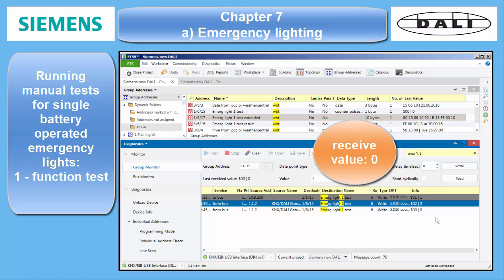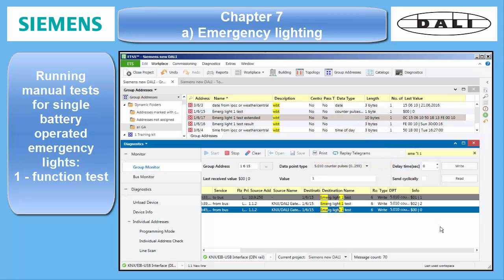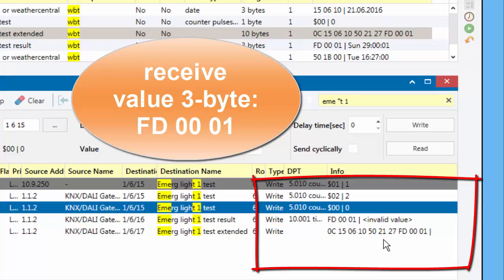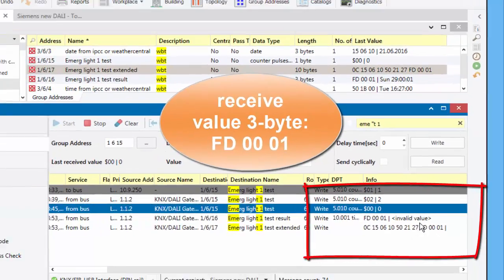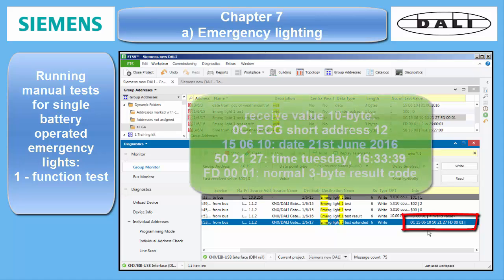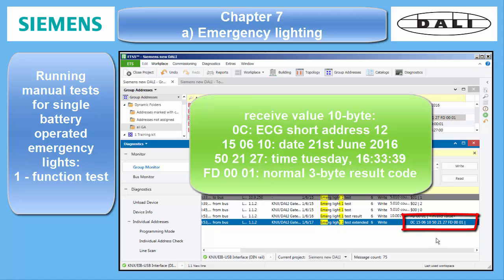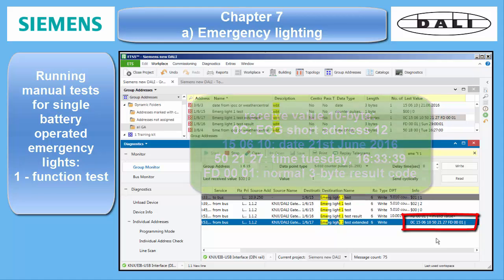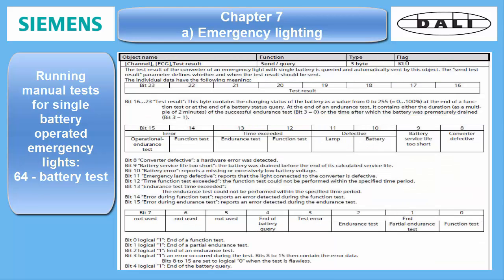After a while, the 3-byte result pops up: FD 00 01, which means battery status 99% full and function test OK. After a short while, the extended test result telegram is also sent. It contains the 3-byte result at the end, plus the ECG short address and the timestamp starting from year, down to the seconds.